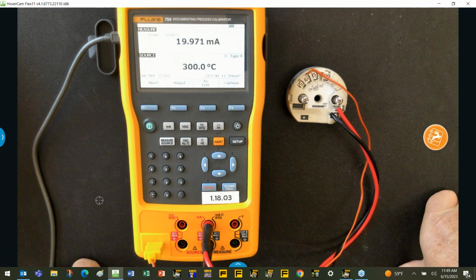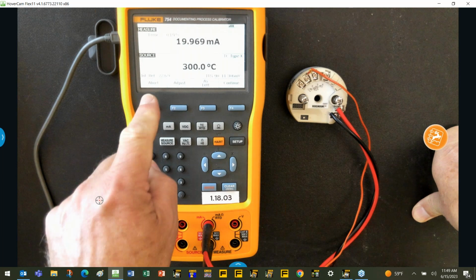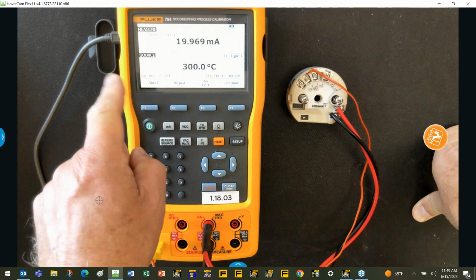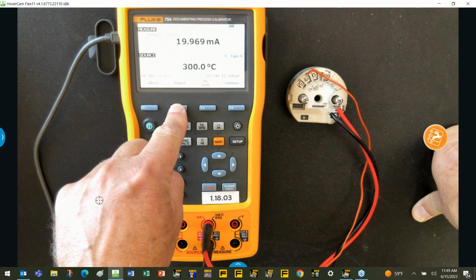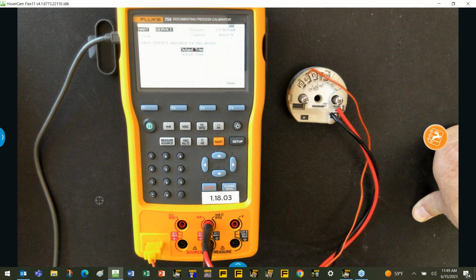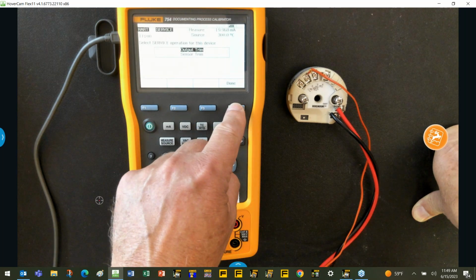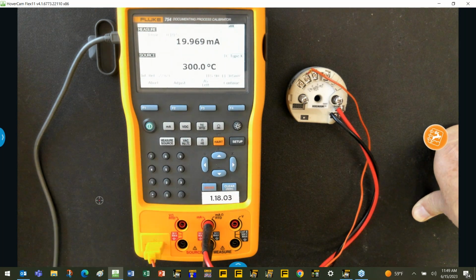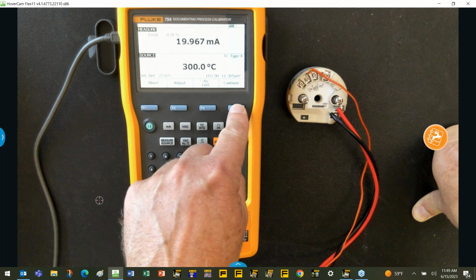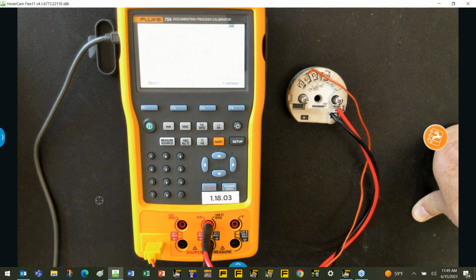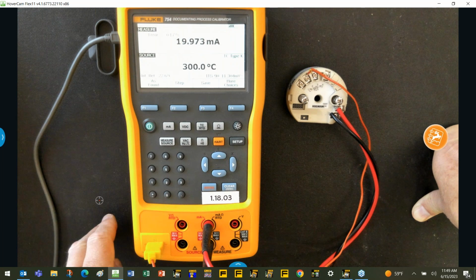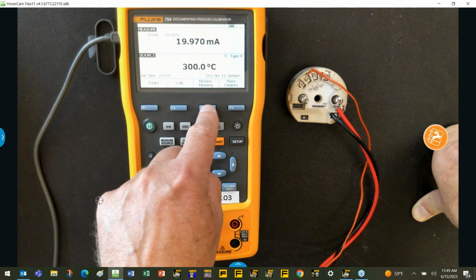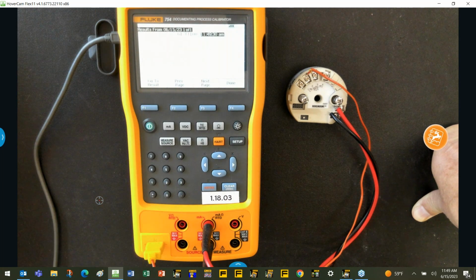Okay, now at this point, if it was out of spec, we would go ahead and do the adjustment like Jim was talking about. I'm not going to do the adjustment because we're already good to go. But you'll notice you go in there and you can make adjustments to both the milliamp output trim and to the input sensor trim of that transmitter digitally. And if we had to make adjustments, we'd go ahead and do the as left and repeat that same test that we did in the as found, but we're good to go. So press continue. You get the message as you complete the calibration. And you're back to the main screen. Now we can go to more choices and check out the memory and see, yeah, there's that calibration that we just did.